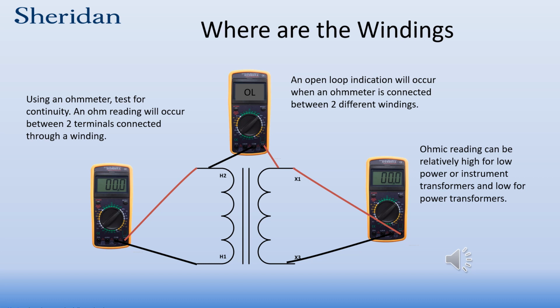One way of doing it is by an ohmmeter. If you use an ohmmeter to test for continuity, there will be an actual reading, an ohmic value, between two terminals that are connected to the same winding. The ohm value will be less for power transformers and higher for instrument or low power transformers. If you connect your ohmmeter between two different windings, you'll get the open loop signal, which means there should be infinite resistance between these two terminals.